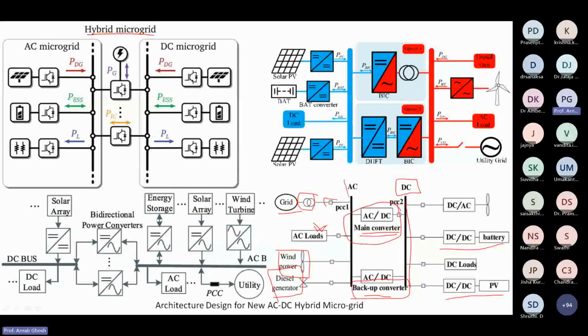Your main fundamental idea is to maintain voltage stability of both the AC bus and the DC bus. For that, you control the AC-DC interlinking converter, or if you're working on the DC bus, you control the DC-DC converter to keep the DC bus voltage stable. When suddenly more load comes, it draws more current, but the DC bus voltage should remain fixed.